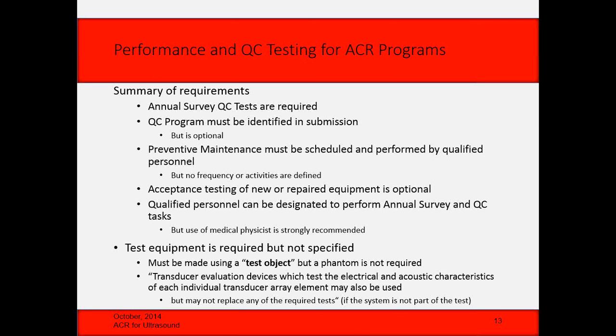So what tools are out there for doing this? Well, back actually many years ago now, we could use the system diagnostics for a lot of this, but the manufacturers started eliminating the probe testing tools about 15, 20 years ago, and most of those only gave a pass-fail result anyway, like the walk test on an HDI system or the dot test on the HP systems, single line test on the Acuson systems. So those were a pass-fail. At least it did tell you whether the transmitter and the element were working.